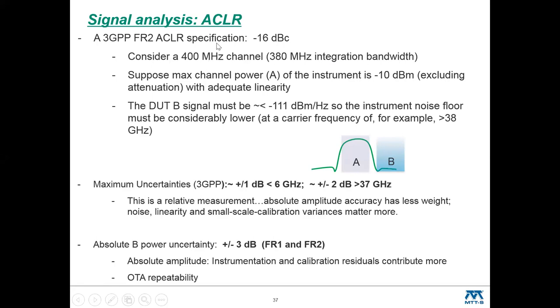But let's suppose we're looking at the widest channel, and this is in the higher frequency ranges, up 28, 30 gigahertz, whatever. A 400 megahertz channel, and the specification is minus 16 dBc, which is essentially the channel power in this little block B relative to that in block A, the in-band. And let's suppose our instrument has a max power, or can support a max power of minus 10 dBm with good enough linearity. So that means to meet this specification, the signal from the DUT in the B channel has to be less than about minus 111 dBm per hertz.